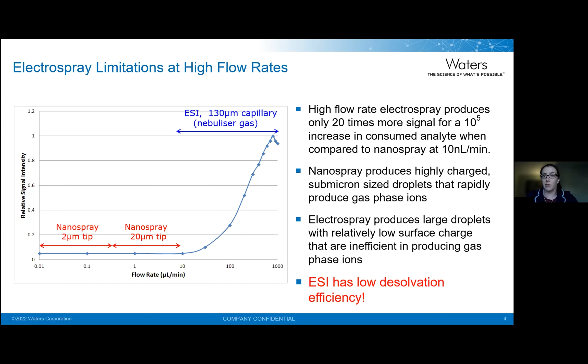But I can tell you from experience, trying to operate nanospray is a pain in the butt. Trying to know if there's a leak when you're flowing at microliters per minute and making good connections that way, it's just not efficient. And for the run times on your LC, you're going to be talking about 30 to 60 minutes instead of 10 to 15. So the takeaway from this slide is that ESI has low desolvation efficiency. It's producing large droplets with relatively low surface charge area, and that's inefficient in producing our gas phase ions.